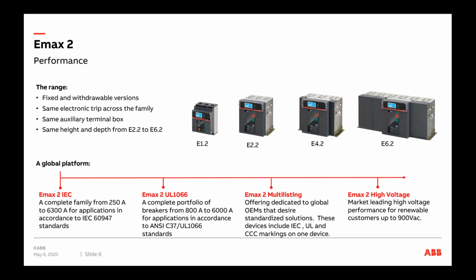The commonality between all the breakers is that the terminal boxes and the connections and the auxiliaries are all the same throughout the whole range. The height and the depth of the breaker has not changed. The only thing which changes is the width. Obviously, with the size of the poles, you have larger width in terms of the size of the breaker. As we go higher on the current ratings, the size goes up. As you saw previously, the panel sizes go up with the larger breakers we have to accommodate larger current ratings.